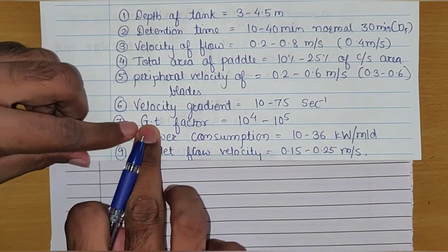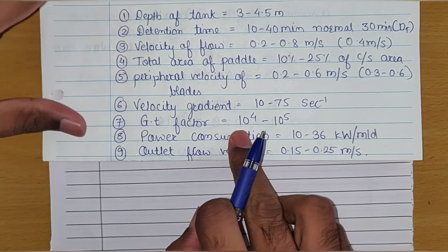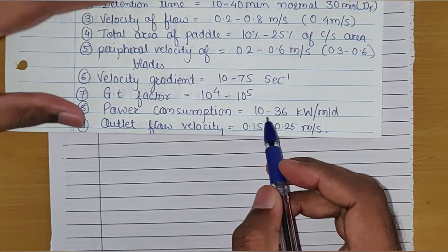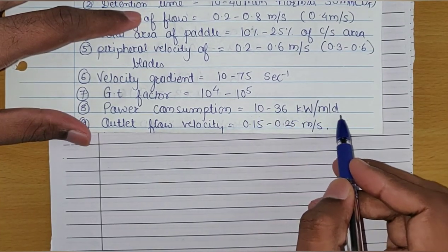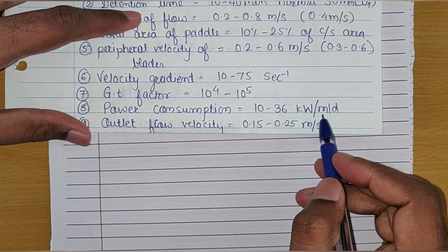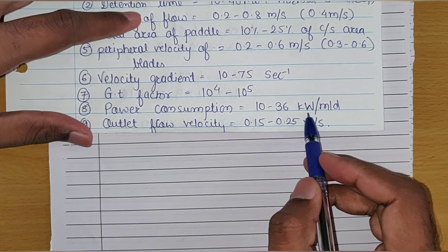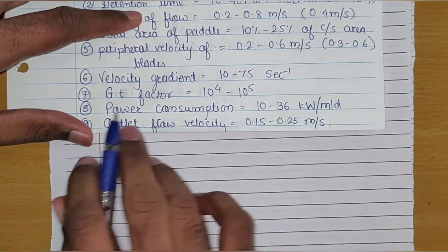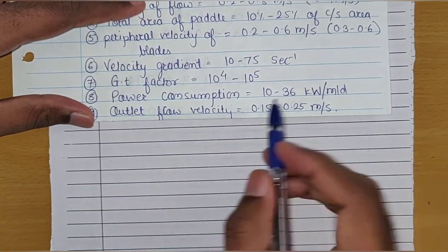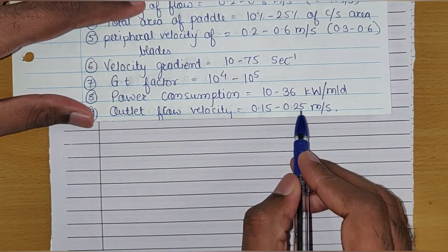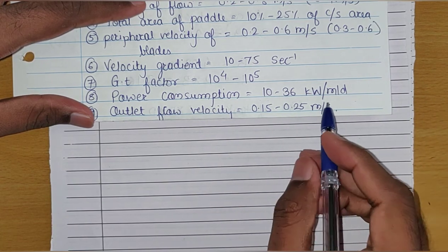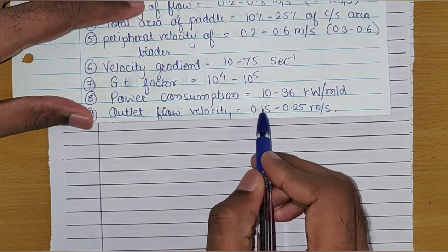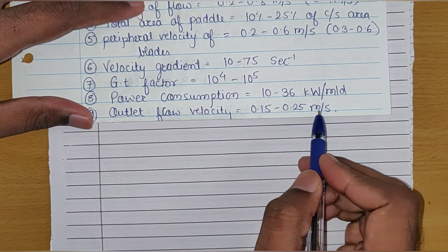The GT factor — velocity gradient multiplied by detention time — should be in the range of 10 raise to 4 to 10 raise to 5. Power consumption should be in the range of 10 to 36 kilowatt per MLD, meaning for the treatment of 1 million liter of water in one day, the power consumption is between 10 to 36 kilowatt. The outlet flow velocity will be 0.15 to 0.25 meter per second — the water going out of the flocculator after flocculation should have velocity in this range.